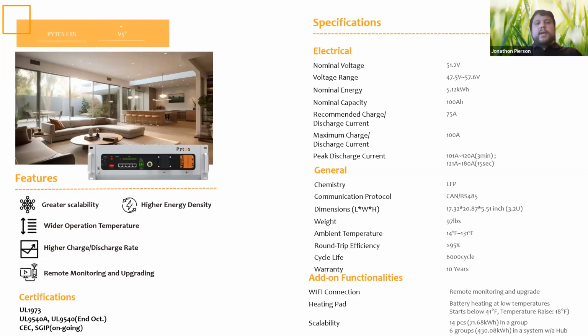For one, it has a built-in heating pad, which allows us to install it in colder temperature environments, including Northern California, northern states, and other areas that get below freezing in a non-temperature-controlled environment. That's a huge call out, even for off-grid communities. This gives us more flexibility in design and gives people who have relied solely on lead acid, due to temperature coefficients, the opportunity to install LFP chemistry instead.